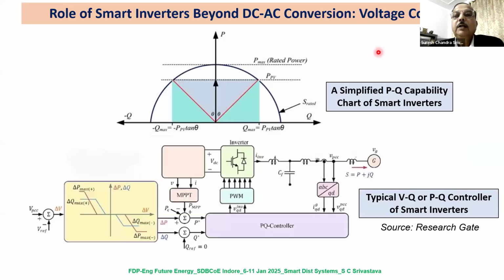Now, converters are not only to interface, but they have a lot of other capabilities which have to be exploited. If you have solar, it generates only real power. Now, where do we get reactive power to control the voltage? Actual reactive power injection is not required to control voltage. Like a STATCOM, you inject a current which is at 90 degree to voltage, which has similar effect as injecting reactive power. So that capability can be exploited by reducing slightly the real power output. You can generate some reactive power. This is a simple PQ curve of a converter interfaced, let us say, solar system.